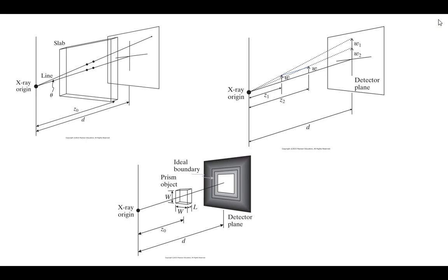I tried to draw that blue line to show those are the same height. The height profile is exactly the same. But towards the origin center, it's going to take a larger angle to reach that first height, which means it's going to hit on the detection plane way up higher than the back. So things towards the front of the body are magnified bigger than ones towards the back because of the depth.